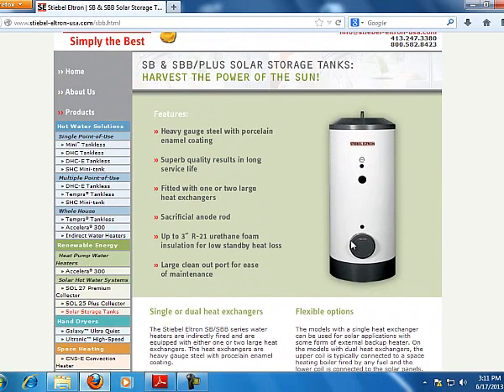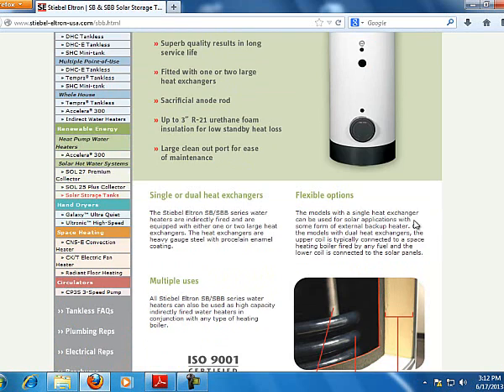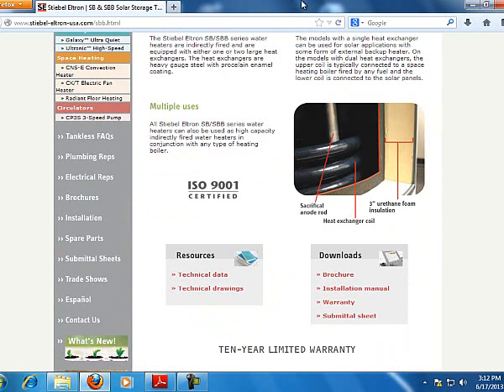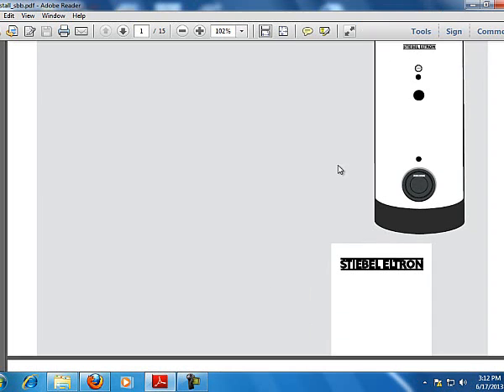Why would we want to use a pressurized tank versus an open tank? Well, the pressurized tank is actually quite a bit more efficient because we can keep the operating temperature just a touch higher under pressurized system, and we also can use the domestic hot water that comes in, be stored in the tank, and then force that water up through. That'll come at a cost. There may be some additional piping and some other concerns we have to worry about, and that's where we're getting permission from the local authority-having jurisdiction will tell us whether this is an acceptable or unacceptable install.